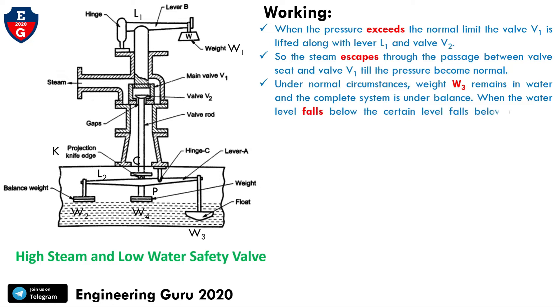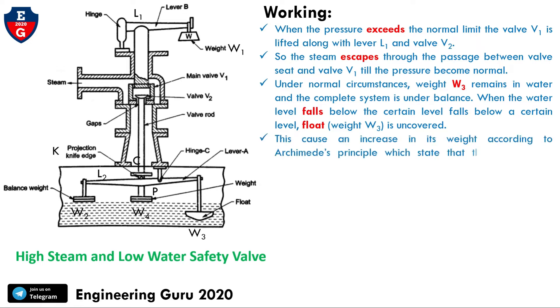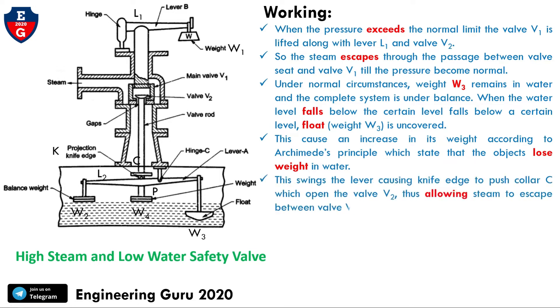Under normal circumstances, weight W3 remains in water and the complete system is in balance. When the water level falls below a certain level, the float W3 is uncovered. This causes an increase in its effective weight — according to Archimedes' principle, objects lose weight when immersed in water. This swings the lever, causing the knife edge to push the collar, which opens valve V2, allowing steam to escape.